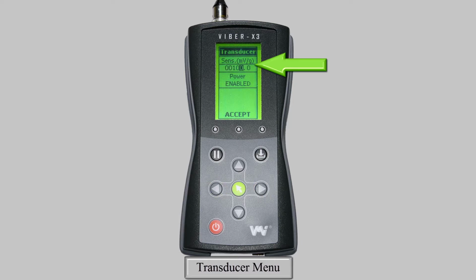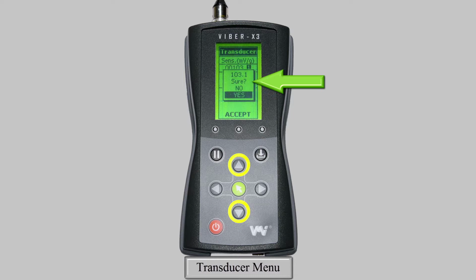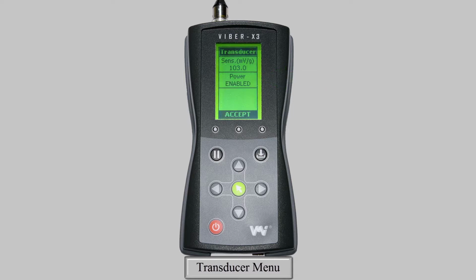Now that an individual digit is highlighted, use the up and down arrows to select a value and the left and right arrows to select another digit. Once the correct value is displayed, press the green key to exit. A pop-up will appear asking whether you are sure about your selection. Use the up and down arrow keys to highlight yes or no, and press the green key. Transducer power is set to enabled when the device is turned on. So when using a transducer with an external power supply, you must first disable this setting before taking any measurements. To exit the menu and save your selected settings, simply press the green key or select the Accept function at the bottom of the menu.